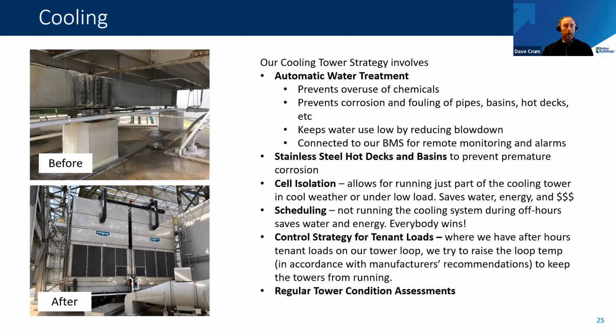What we'll do at night or on the weekends is we'll actually run those in a bypass and bypass the cooling tower. That saves water, and it also saves us fan power and a little bit of energy as a result. We do have a safeguard on the BMS in the background, so if the water loop does get too hot, it will bring the cooling towers back on.